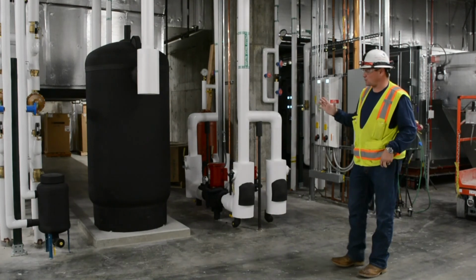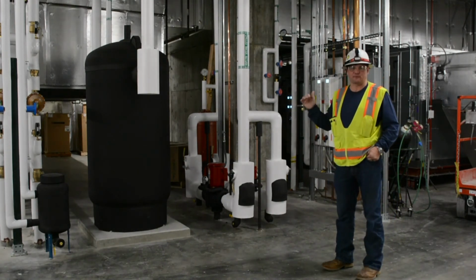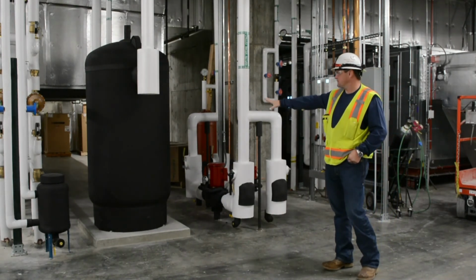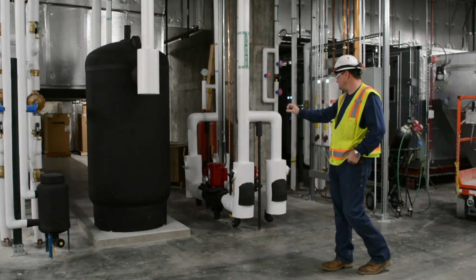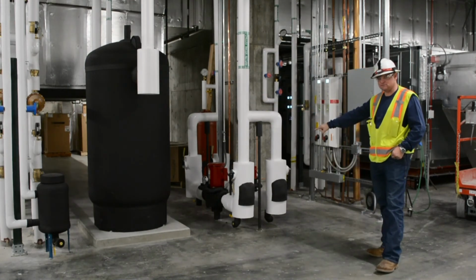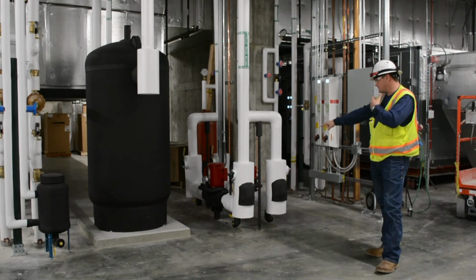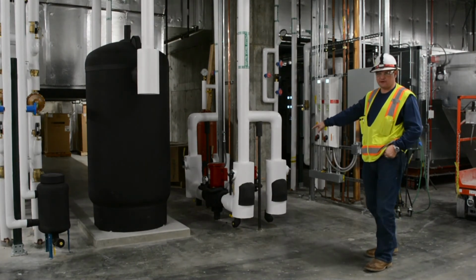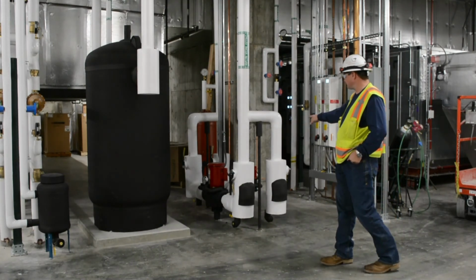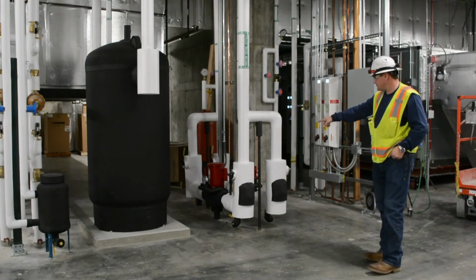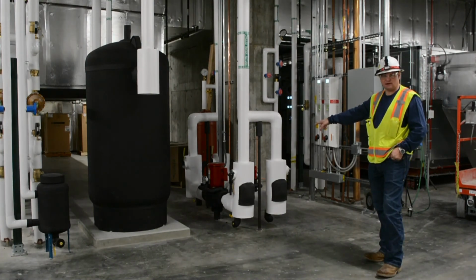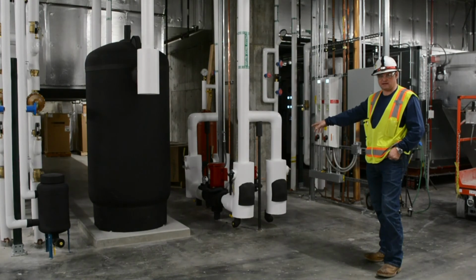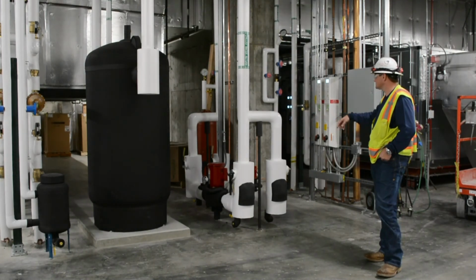This is the backup chilled water system for the new data center for the research tower. This is simply a volume tank. You've got your chilled water pumps. They're inline pumps. They don't need any alignment or any adjustment. They operate off of a variable frequency drive. The motor lubrication frequency is the same, 8,000 hours, 1.5 ounces of grease per bearing.